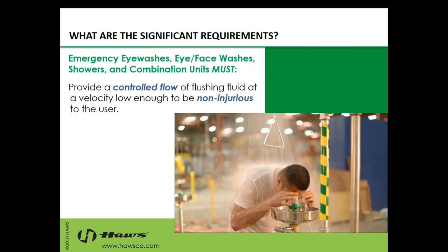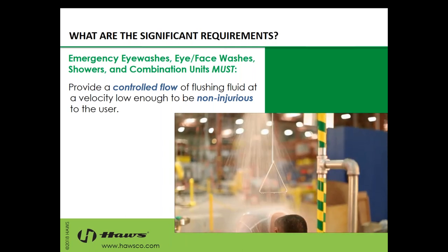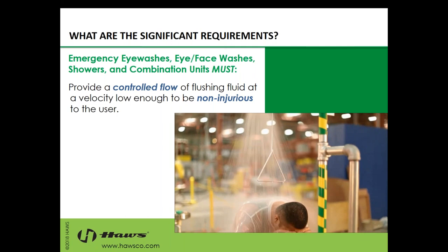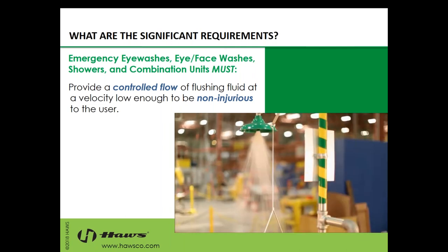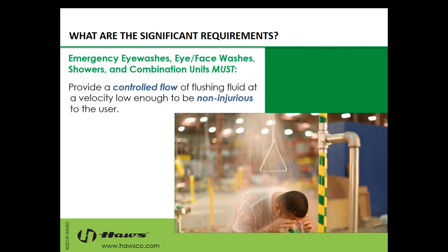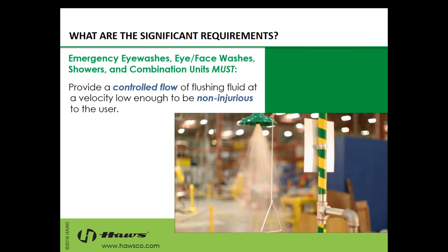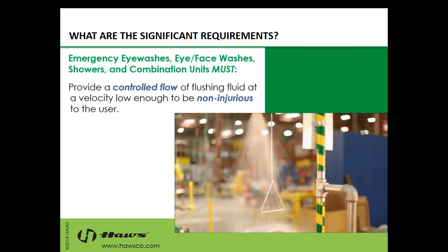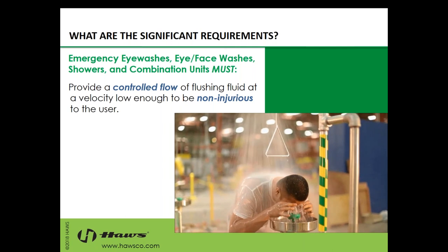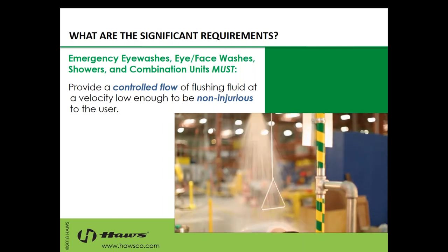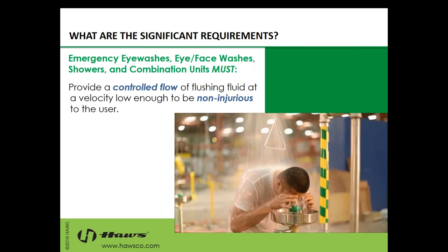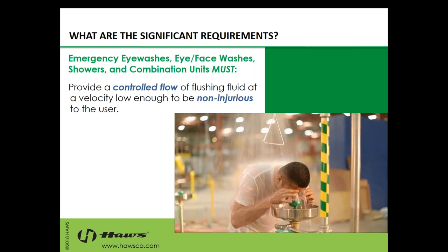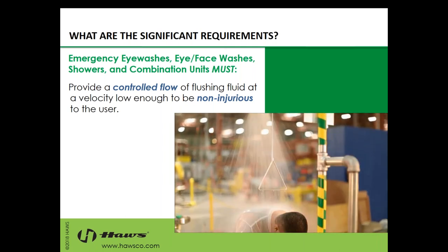And this is typically a pretty serious issue, as a lot of times in facilities, we can see they've plumbed too much water or too little water. In this example, too much water would lead to an injurious flow. We have an eye wash head that's shooting 20 feet one way and 20 feet the other, and we like to call those brain washes here. But we want to provide, again, a comfortable experience, and we don't want to blow their eyes out on top of them already being injured.